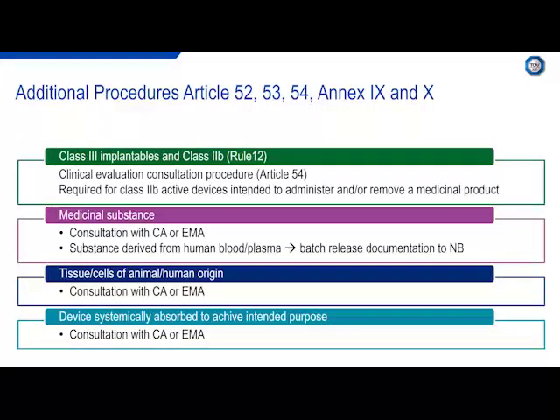And also to highlight some of the special procedures. So there are additional procedures in accordance with Articles 52, 53, 54, Annex 9, and Annex 10. So for example, for class 3 implantable devices and for class 2B, that is Rule 12, we will need to go through a clinical evaluation consultation procedure, which means if the notified body has evaluated the clinical evaluation of the manufacturer, then the assessment result of the notified body needs to be forwarded to the medical device expert group, and they also have to evaluate this, but we come to that later. The same is true for devices that administer or remove a medicinal substance from the body. With medicinal substances, we have to consult with a competent authority or the European Medicines Agency.